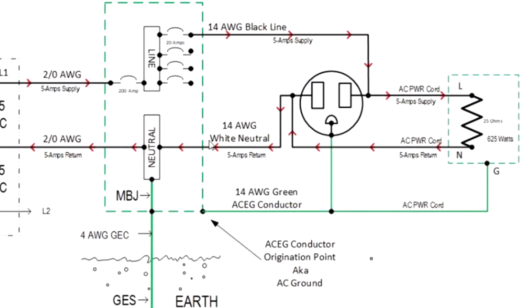Okay, so we turn the power on. This device can be anything, but it's drawing about 600 watts. At 600 watts, it should draw about 5 amps of current with 120 volts applied. If you look, I've got these little red arrows showing us the current path in normal operation. You can think of this as a battery or anything you want right here. The current leaves on the line conductor, goes to the fuses, the distribution, out on the line, through the device, and then returns right back on the neutral conductor, right back to the transformer. All right, everyone see that?